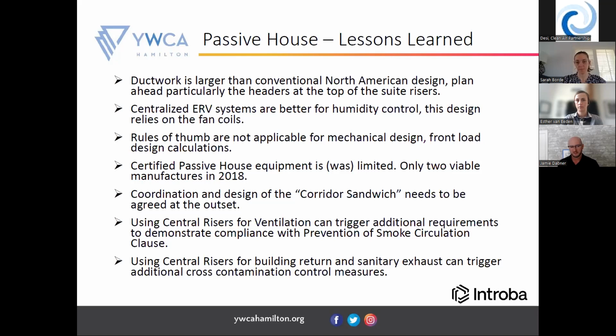As Esther was saying, rules of thumb don't really apply for buildings like this, like doing it the same way as a regular SB10 or a building code building you've designed before. You really have to do the calculations early and upfront, and the loads that show up are so much smaller than the engineering team is used to. It's actually hard to get equipment and fan coils sized correctly because the loads are so small. You can get it from Europe, but having something available in North America is a little bit difficult.